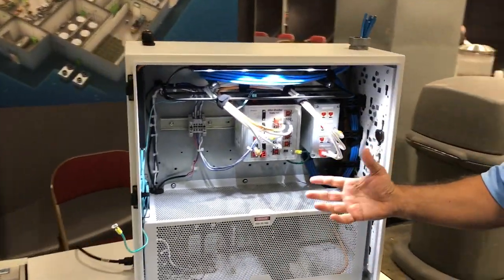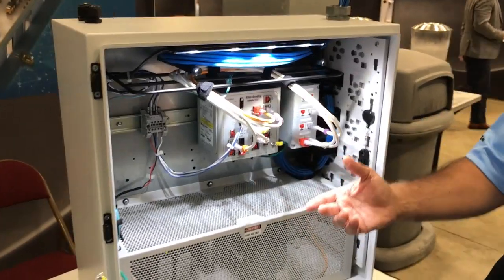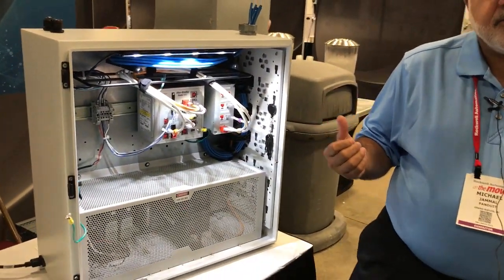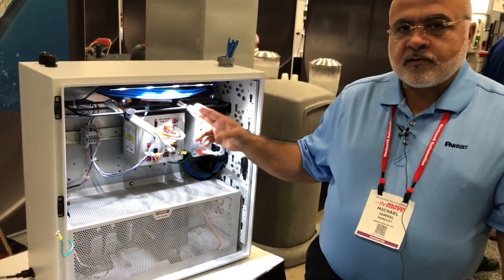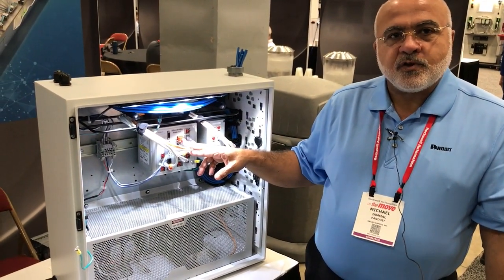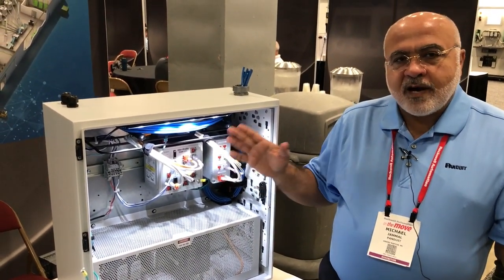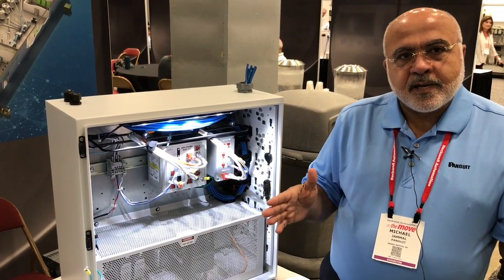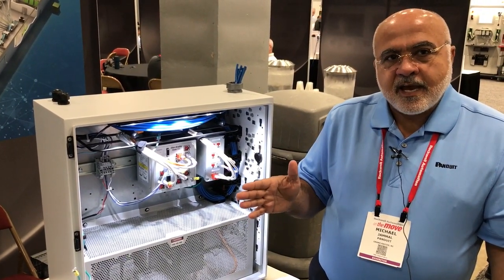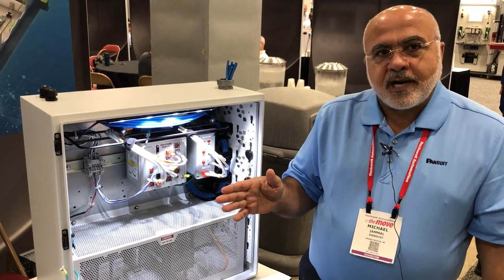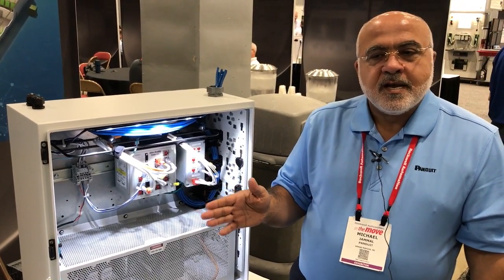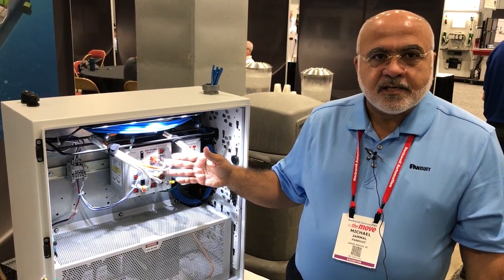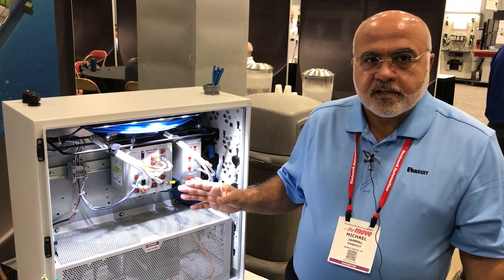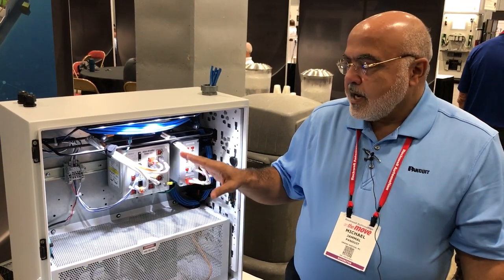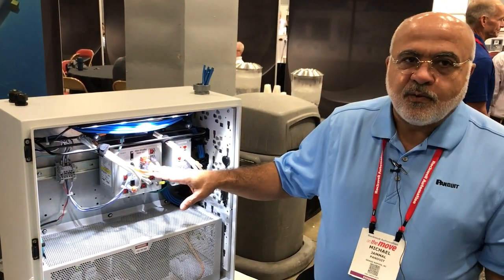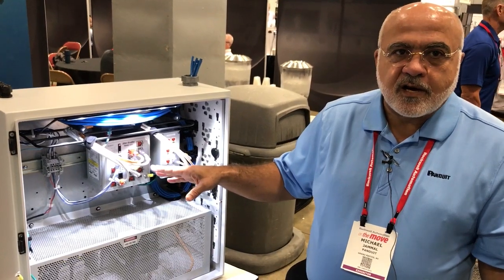Basically, we take the switches and all the communication components out of the control cabinets. The reason is, when troubleshooting a switch, you need to have it live. If it's inside a control system near a PLC, you'd need to shut down the power to get into the controller. You don't need to shut down power in a zone enclosure because it's low voltage, and you need to access it while it's still hot to do your diagnostics.